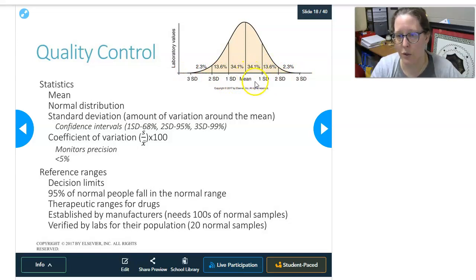And so research and quality control in the lab have determined that a 95% confidence level is adequate. So we can say that as long as the points fall within 2 standard deviations above and below the mean, it's a 95% confidence level. We can say with pretty good reliability that our testing is accurate and that we're good. If it falls outside of 2 standard deviations, then there's a problem with that analyte and with that particular control level. The standard deviation is basically the amount of variation around the mean.